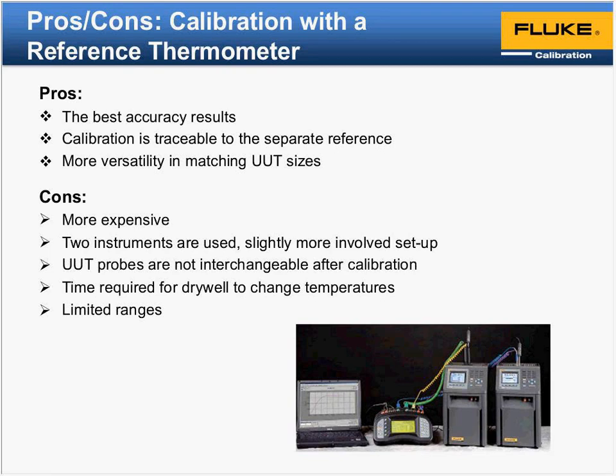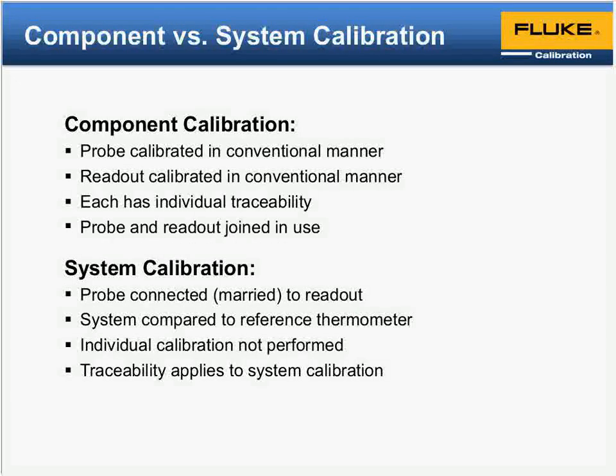Okay, the next question. You talk about using a Drywell calibration, that there's an internal sensor in the Drywell that's mapped to the readout and the reference. Could you just talk about the accuracy of each one of those? The sensors that are used in the heat sources are typically an RTD. They may be class A or something. For the accuracy, the readout or reference. Again, the heat source accuracies are typically in the tenths. Sometimes we're able to achieve a digit like 0.02.